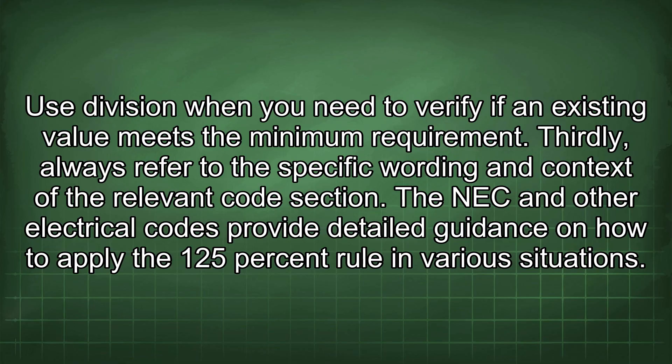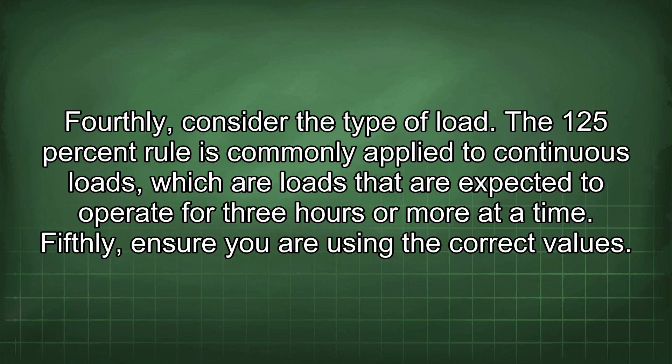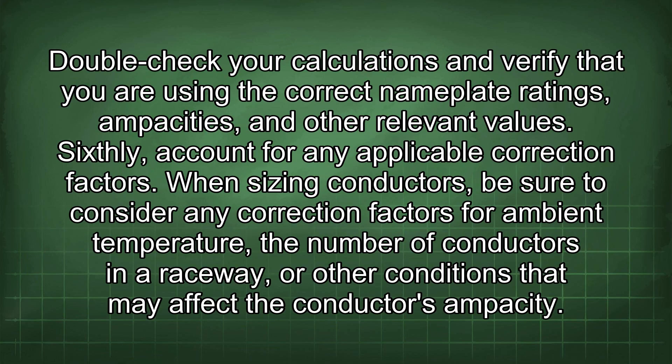Third, always refer to the specific wording and context of the relevant code section. The NEC and other electrical codes provide detailed guidance on how to apply the 125% rule in various situations. Fourth, consider the type of load — the 125% rule is commonly applied to continuous loads, which are loads expected to operate for three hours or more at a time. Fifth, ensure you are using the correct values; double-check your calculations and verify nameplate ratings and ampacities. Sixth, account for any applicable correction factors for ambient temperature, the number of conductors in a raceway, or other conditions affecting conductor ampacity.